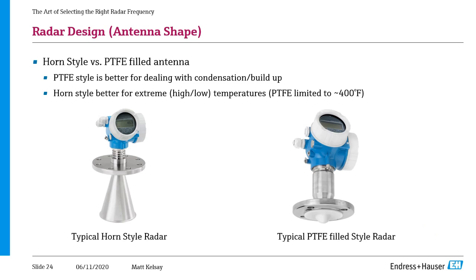So this shape will collect condensation on it, water droplets will form, but because of that half golf ball shape, they tend to collect up on that and then just drip right off the end, which doesn't really have any effect on the radar. However, if you look at the big horn style radar, those also collect water droplets up on the inside of that big horn, and those water droplets will actually absorb a lot of the signal that's sent out from the radar, making the measurement much more difficult. The one downside, I'll say, to having this PTFE style radar is that we are limited by temperature. So that's roughly 400 degrees F, just a little bit below. Whereas with the horn style radar, we do have versions that allow us to reach much higher temperatures.